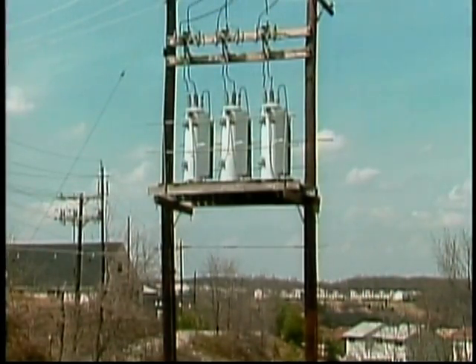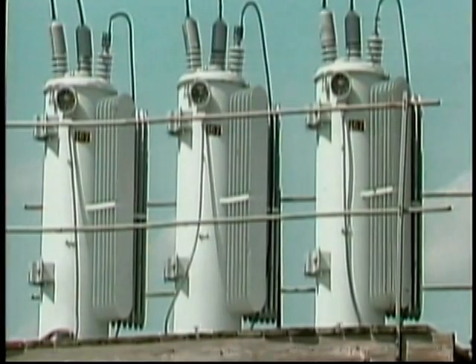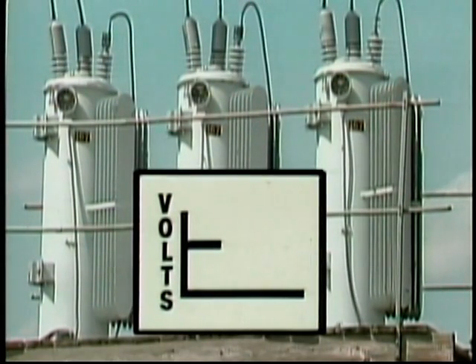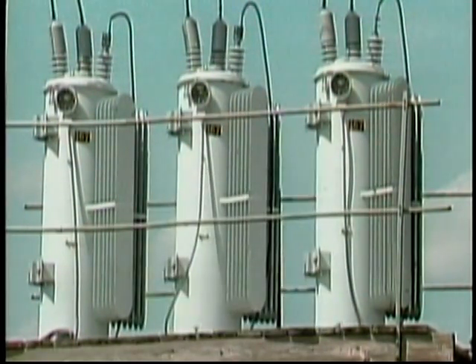A device that looks similar to a distribution transformer is the voltage regulator. Like a transformer, it's cylindrical in shape. Its function is to maintain voltage within a given range. If system conditions cause voltage to drop, the regulator brings it back up. If conditions cause voltage to rise, the regulator lowers it. There are several features of a voltage regulator that help to distinguish it from other overhead distribution equipment.